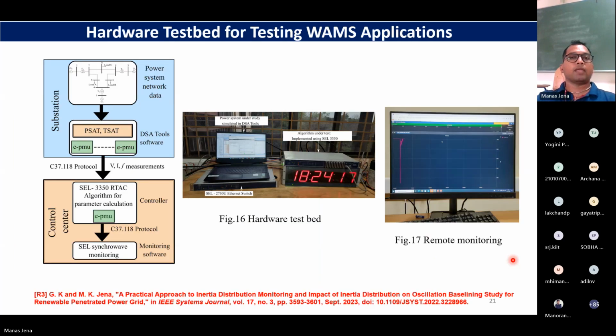We also tested that on a test bed that we have in the lab. We don't have the luxury of getting actual PMU data, so we simulate the system. The Northern Regional Power Grid was simulated on a simulation platform. We use DSATools software from PowerTech Labs. We very rigorously use this for power system modeling, and they have one add-on called ePMU. It's a software PMU, so it can stream measurements using the C37.118 protocol.